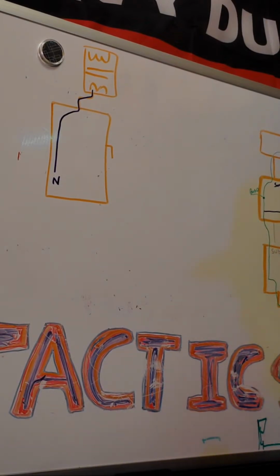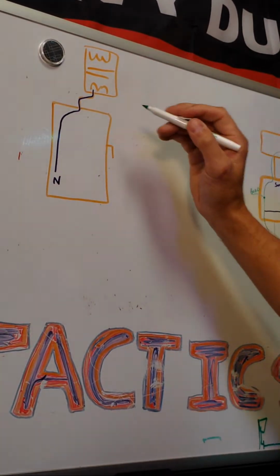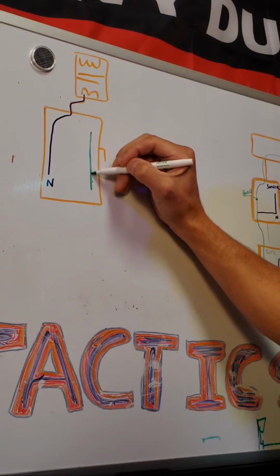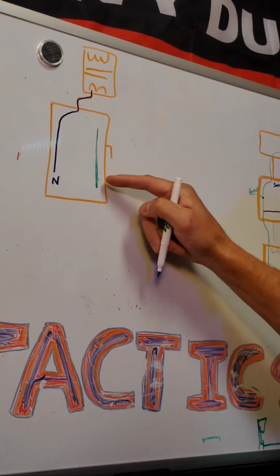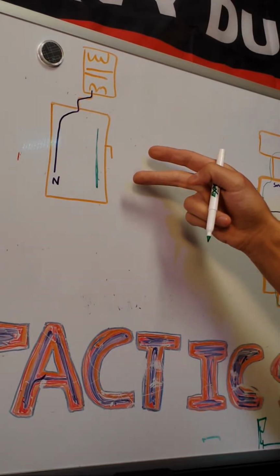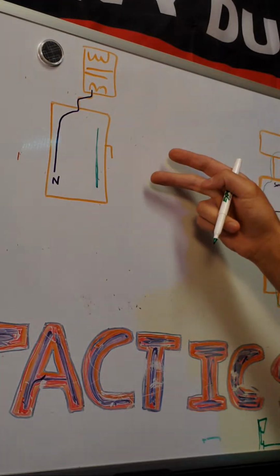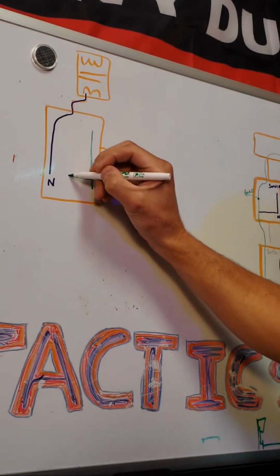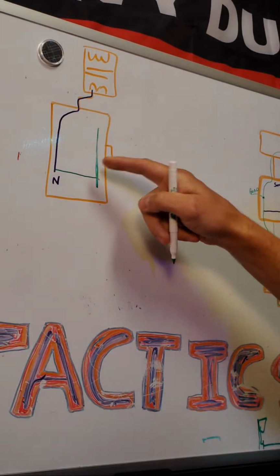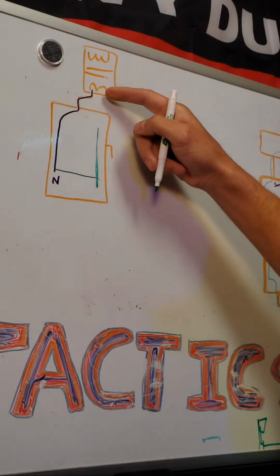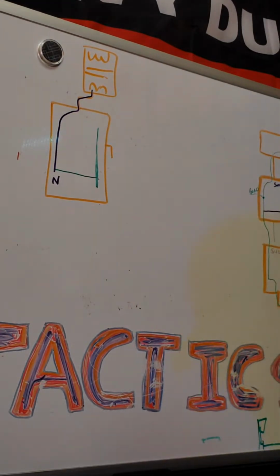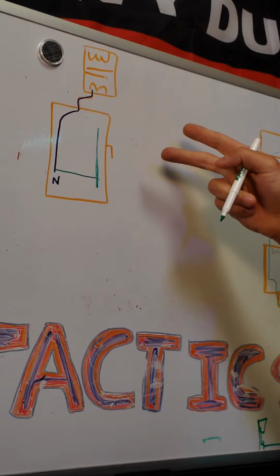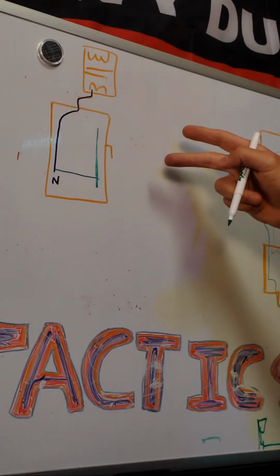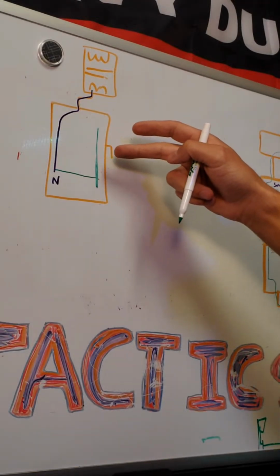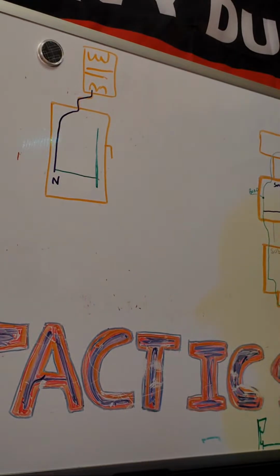Now, this is where our equipment grounds are born, inside this service equipment. And you have a ground bar here. The ground bar's job is to get all of the current off of all your equipment ground conductors, like on your receptacles and things. Its only job is to get current back to the neutral so that we can go back to the source to trip the breaker. That's the only job. So if we've got anything that's metal likely to become energized, anything that can become energized, especially metal, it lands on your ground bar. And you're only going to bond here at the source.